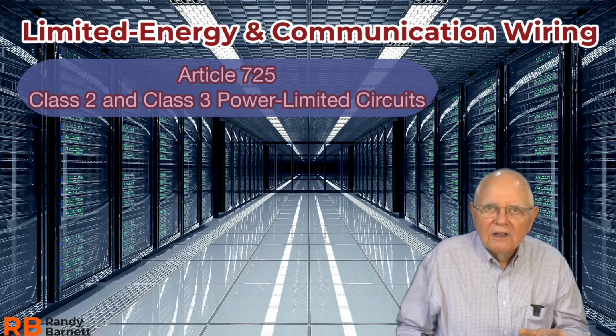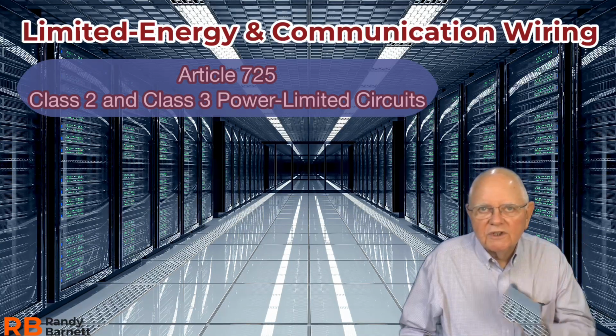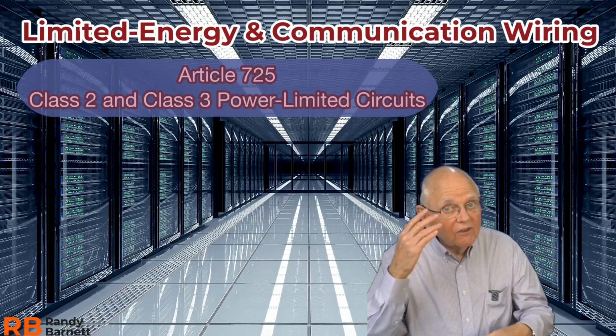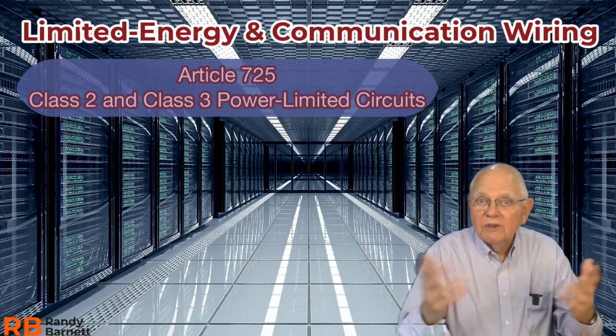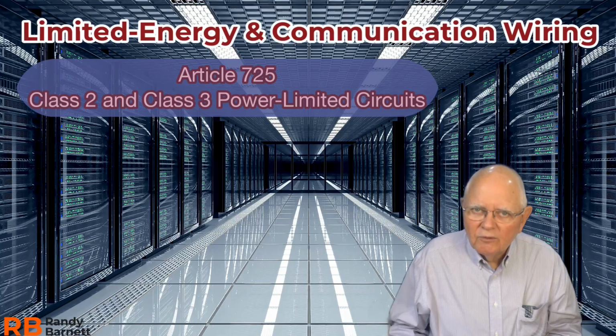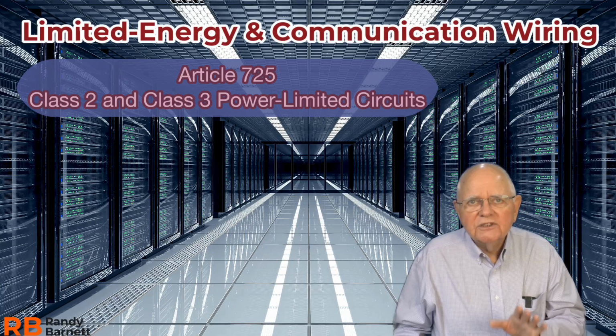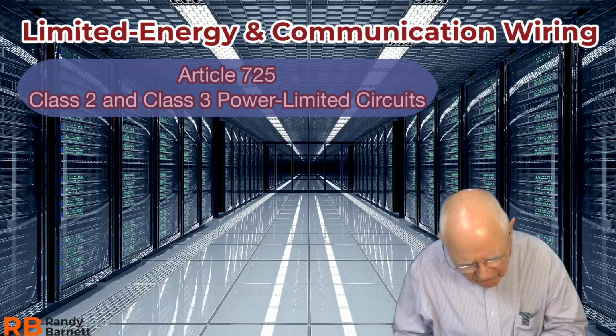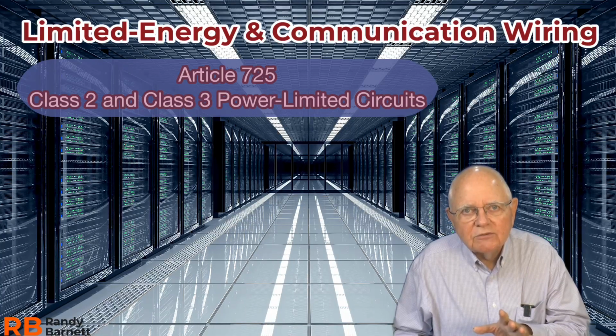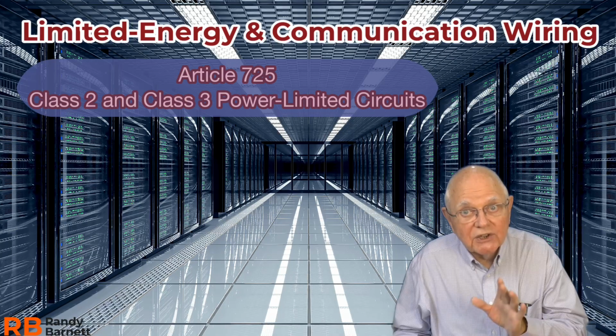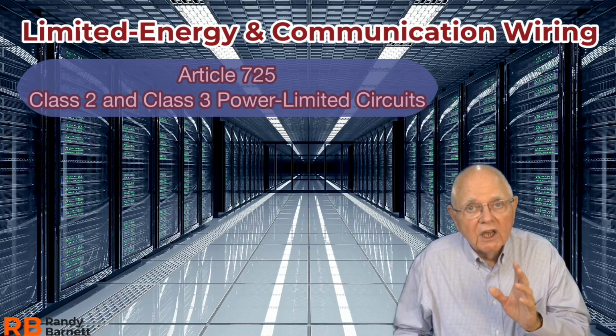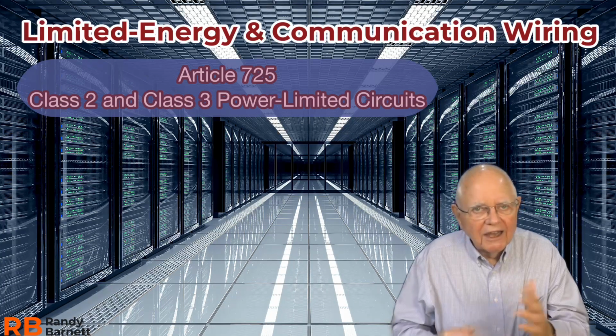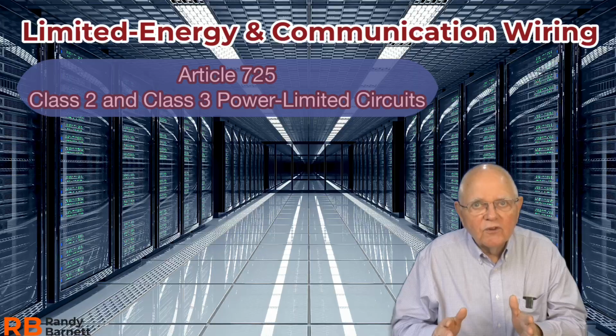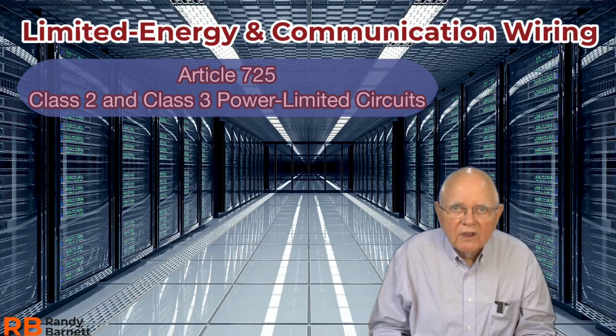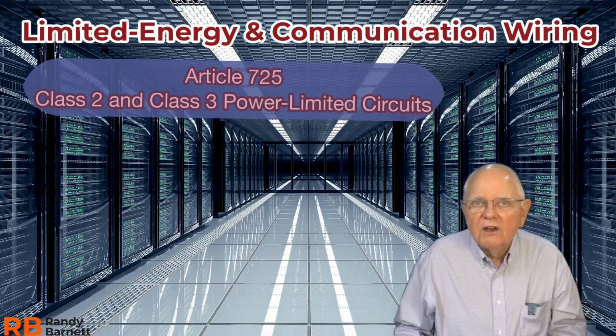It's a very short article. It's once again shorter than a page. And once again, we have the transmitter and receiver. Power is limited between these two. Excellent informational note. So what I'd encourage you to do, take a look at the article on Class 4, fault mitigated power systems, and read that informational note under the scope, 726.1, so it's Article 726. Look at 726.1, a lengthy informational note that gives you lots of information to help you understand these systems, as pretty soon you might be involved in installing these.